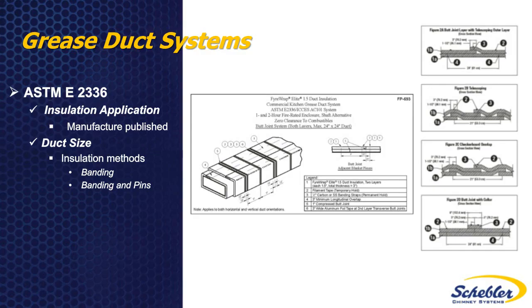Application of the insulation to be considered fire rated would really be found in ASTM E2336. And in the testing done under ASTM E2336, the insulation manufacturer is going to publish how that should be conducted so as to meet the test requirements they've gone through. So based on the aspect ratio of the duct, so the inner surface area, and also how they're going to support this, there's going to be several methods of banding, pinning, overlap of the insulation, overlap of the seams of the insulation to make sure it complies with the engineering standard to allow it to be utilized as a fire-rated shaft.